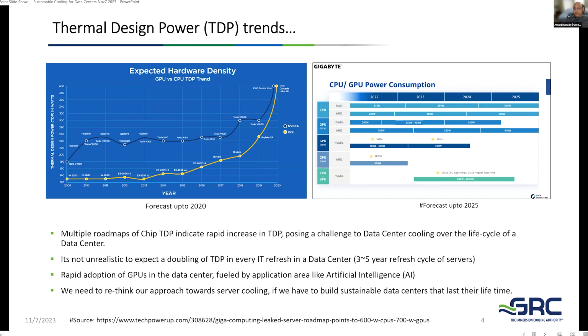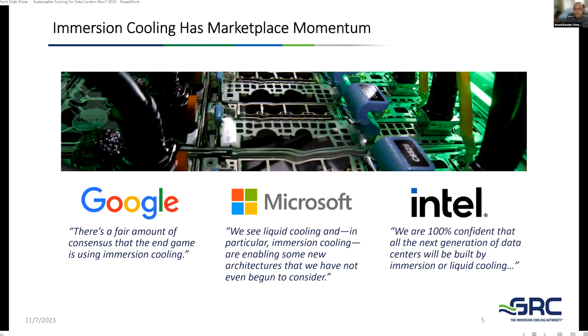So what is the solution? We need to create a data center infrastructure today which is easily able to cater to the requirements of the future while being more efficient in doing so, right? And that is where the answer is not to increase the number of fans or reduce the temperature of the air. That is not an answer, because both these actions only increase the energy consumption and reduce the efficiency of the overall system. Now you would say that, okay, you are from GRC and you have a technology called single phase liquid immersion cooling. So it is very natural. You will say this is a very good technology, right?